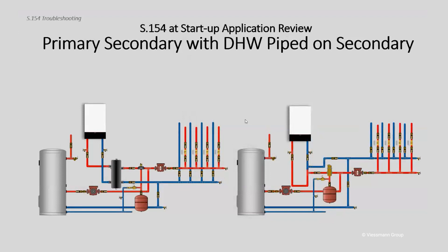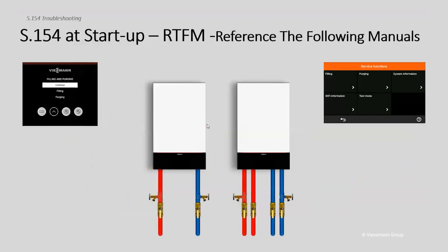Another possible application — say it's a retrofit and you're adding a boiler to an existing system where tanks are already connected on the secondary. You can deactivate the diverting valve in programming and commissioning to tell the boiler the domestic hot water system is not connected directly. There are relay outputs on both boilers for that domestic hot water pump. Now the diverting valve stays in the heating position even during domestic hot water operation — a bit easier to purge since the diverting valve stays in one position.